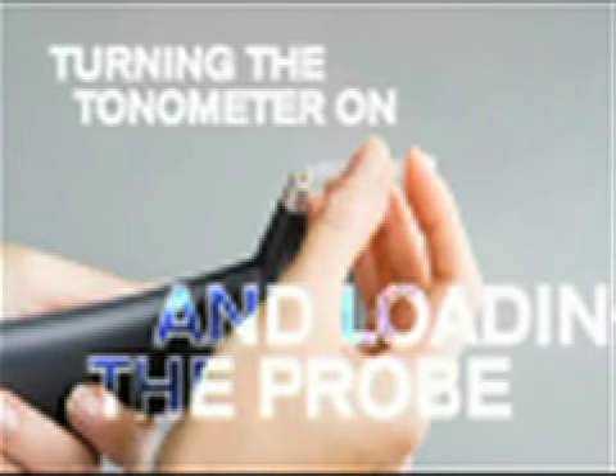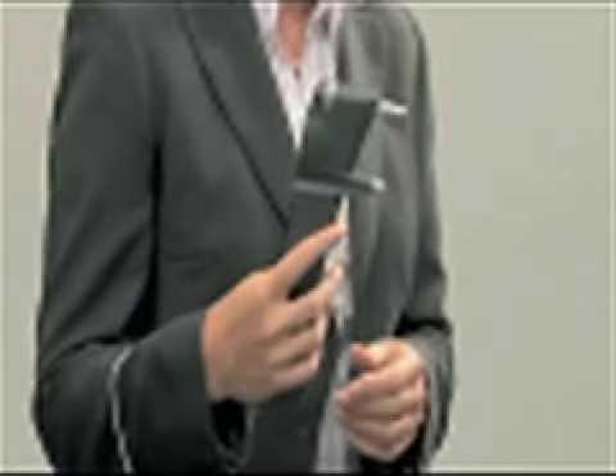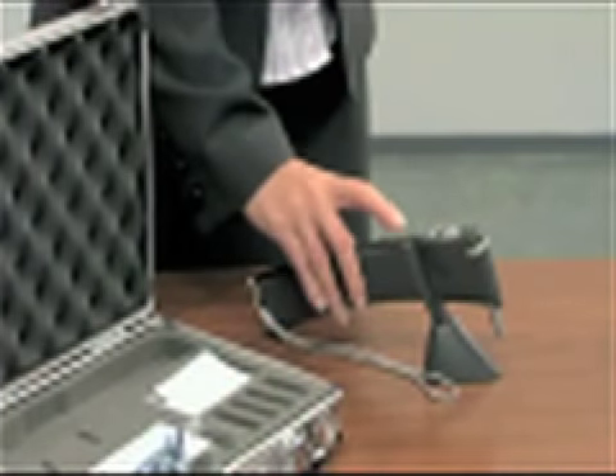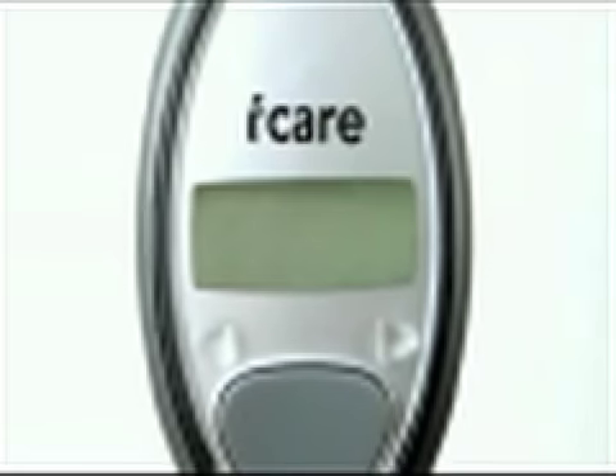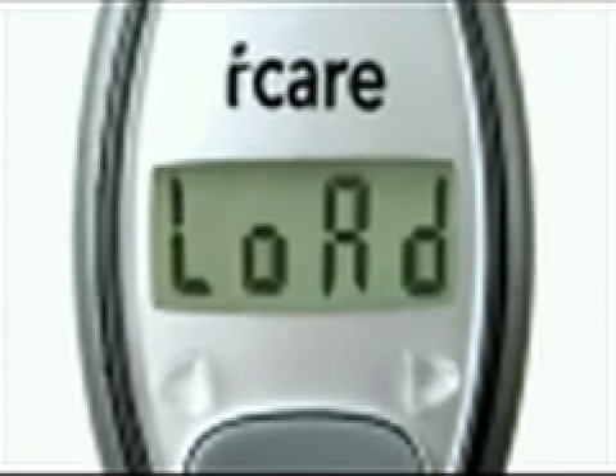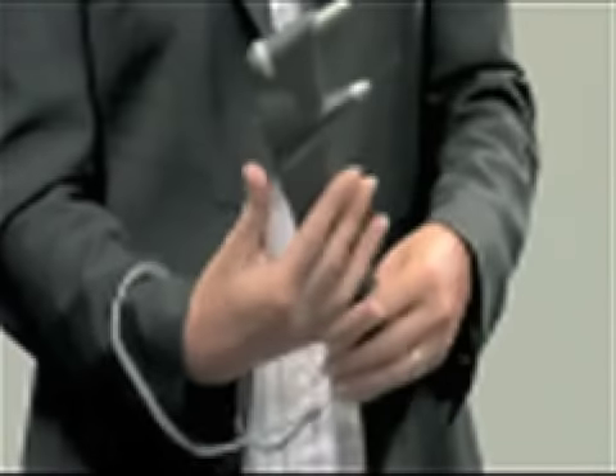Turning the tonometer on and loading the probe. Before using the icare tonometer, insert the batteries and fit the wrist strap onto the tonometer's wrist strap attachment. Start by pressing the measurement button to turn the tonometer on. Load the probe into the tonometer when the display shows Load. To load the probe, open the disposable package, place it against the collar component, and drop the single-use probe into the collar.